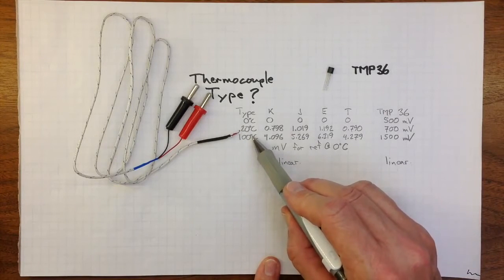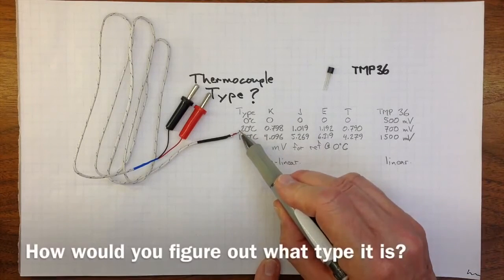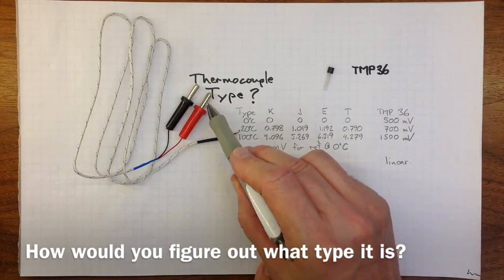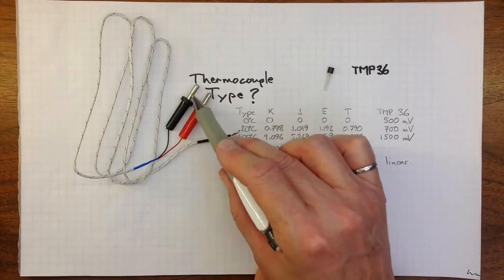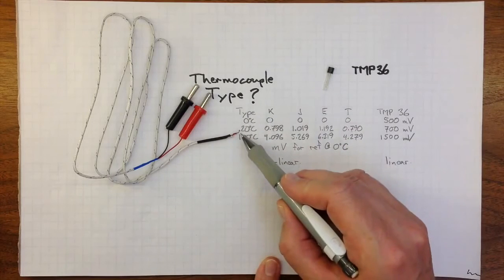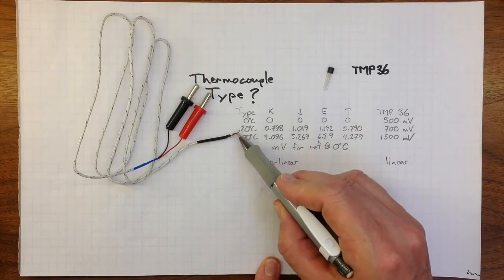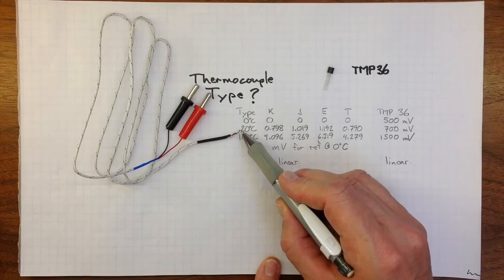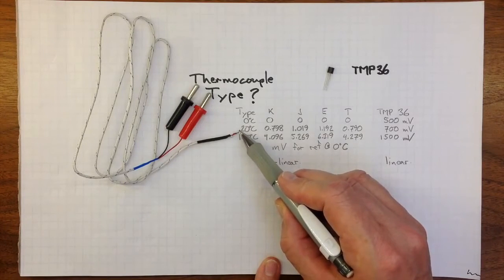The key thing here is it's the temperature of the bead that determines what the voltage is that we'll see on those two wires there. So it's not the temperature of the air around the bead. It's the temperature of the actual junction, the temperature of the actual transducer.